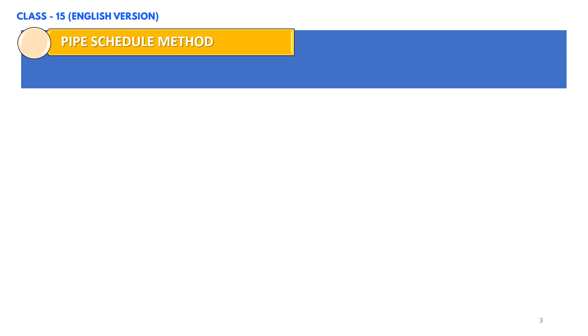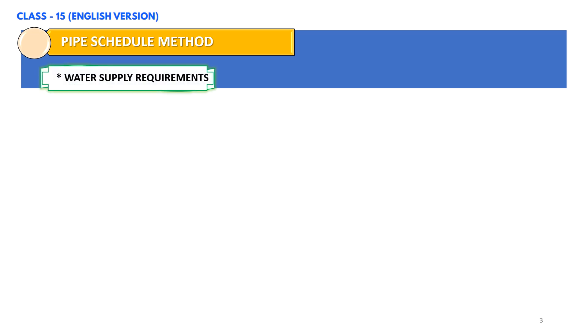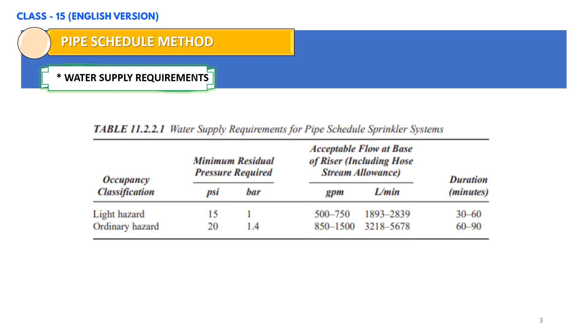In this slide, we shall go through water supply requirements for pipe schedule sprinkler systems. Table 11.2.2.1 shall be used in determining the minimum water supply requirements for light and ordinary hazard occupancies protected by systems with pipe sized according to the pipe schedules of section 23.5, which shall be discussed in later slides. Pressure and flow requirements for extra hazard occupancies shall be based on hydraulic calculation methods only.